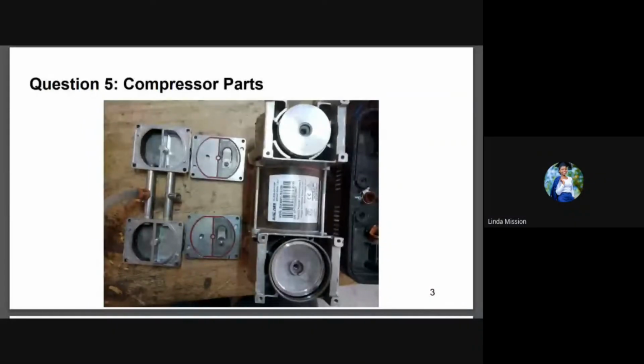Thank you once again, Maui. The double wobble compressor of an oxygen concentrator has four main parts, which include the head gasket, two valve plates, the piston, and the motor. As you can see in the graphics, those are the parts that I've mentioned. These parts work together with some subparts to pressurize air for nitrogen adsorption. Each valve plate has two one-way valves, which are also called flapper valves, and the head gasket is divided horizontally, with one side being the inlet and the other side being the outlet.